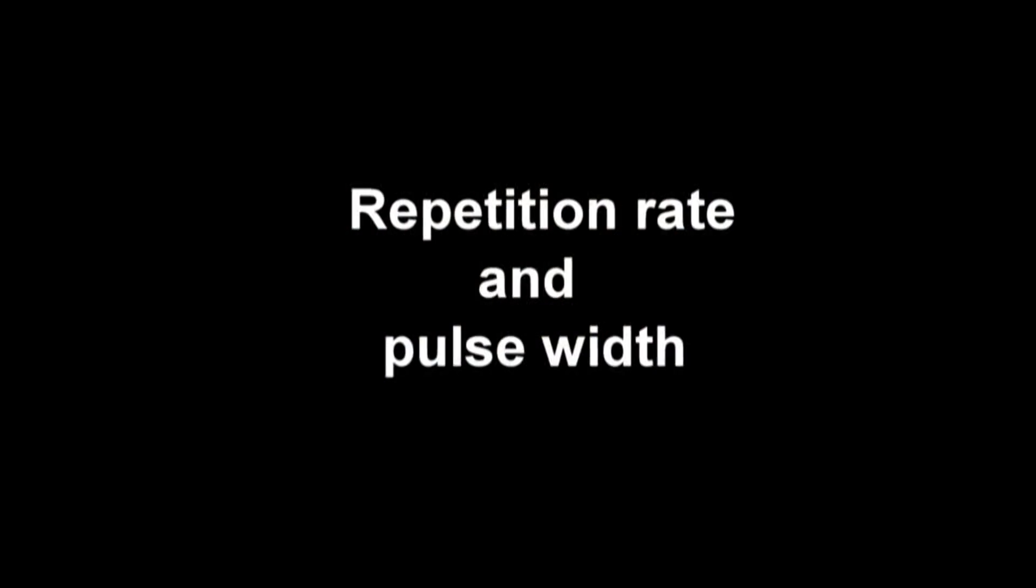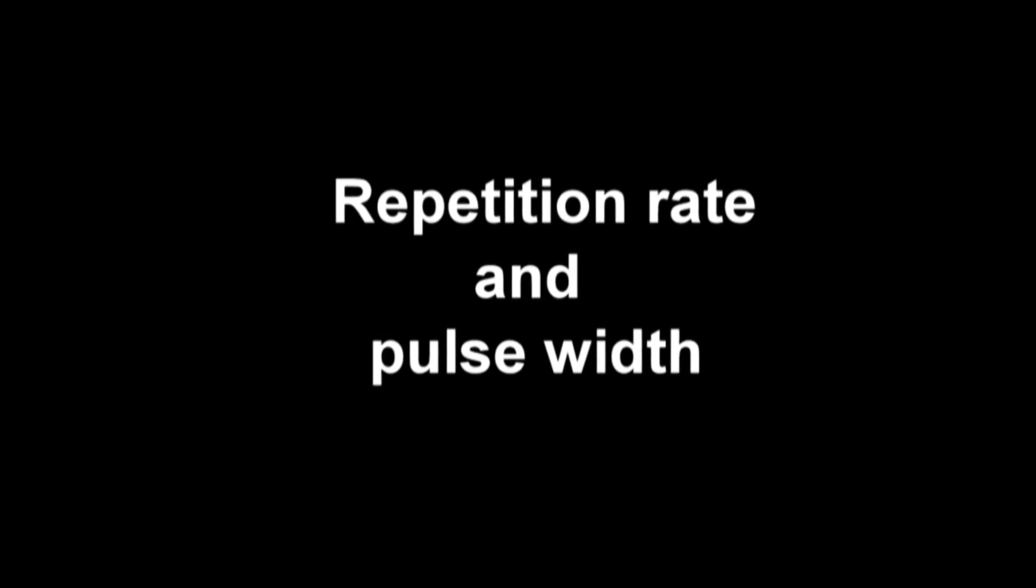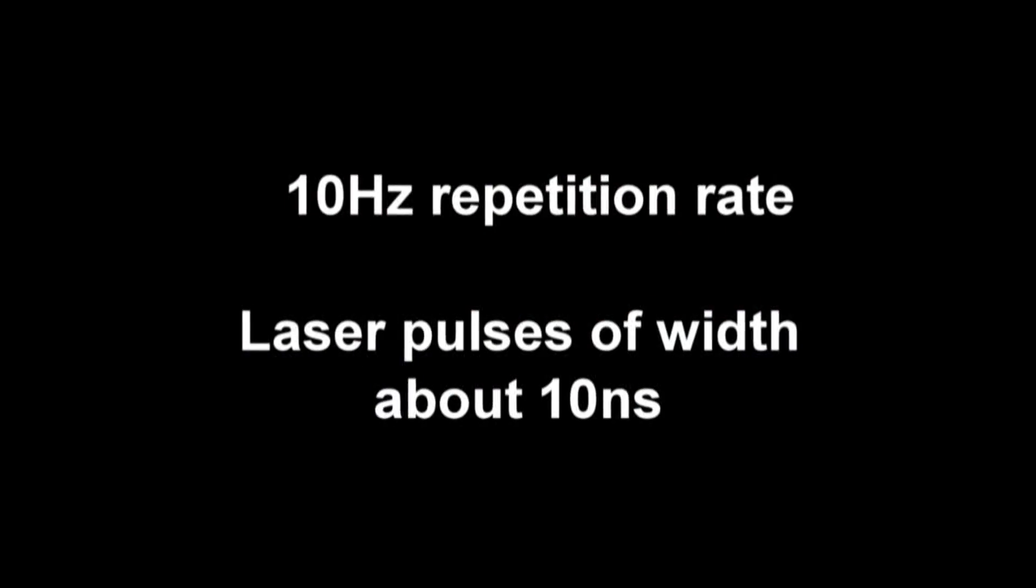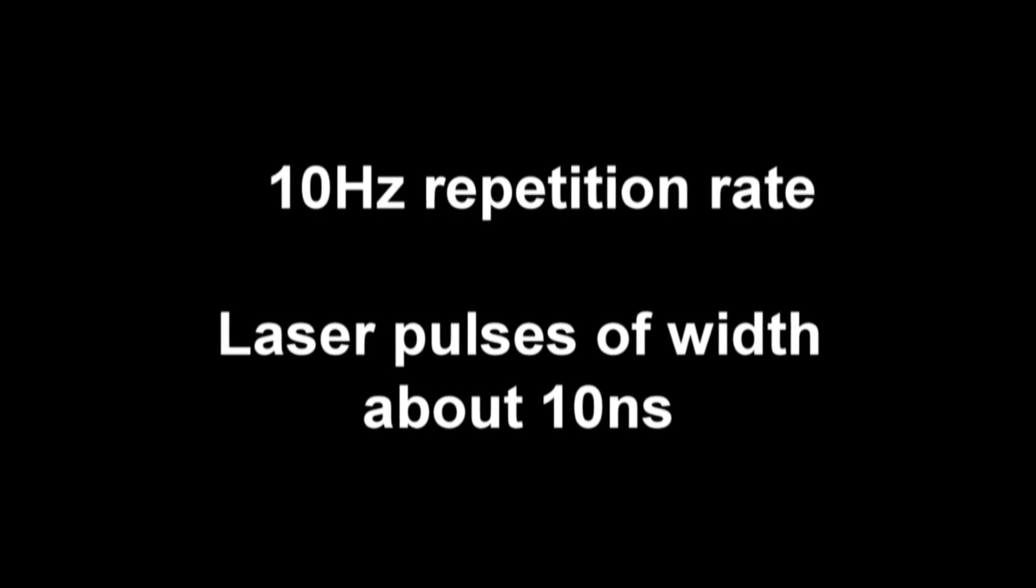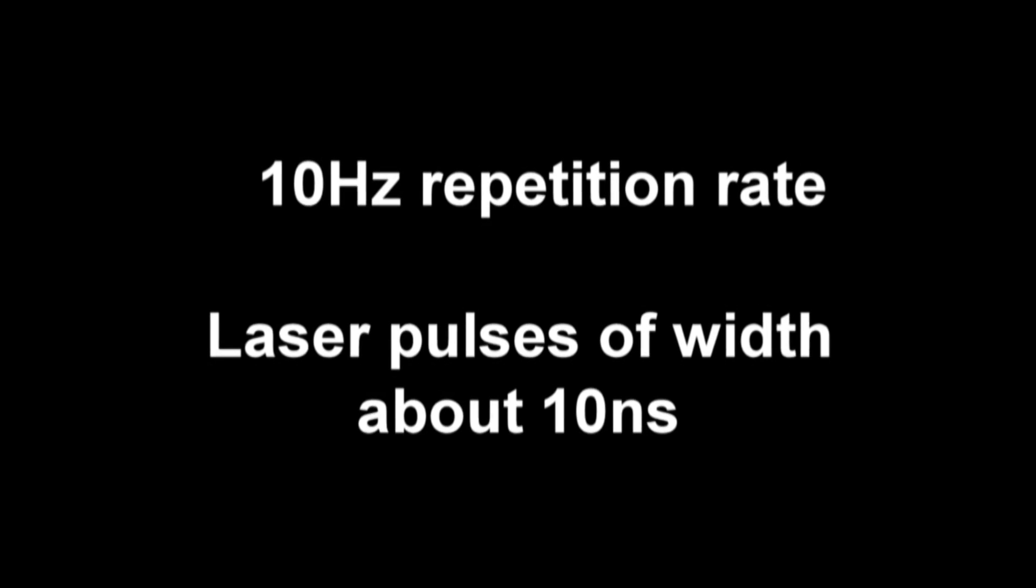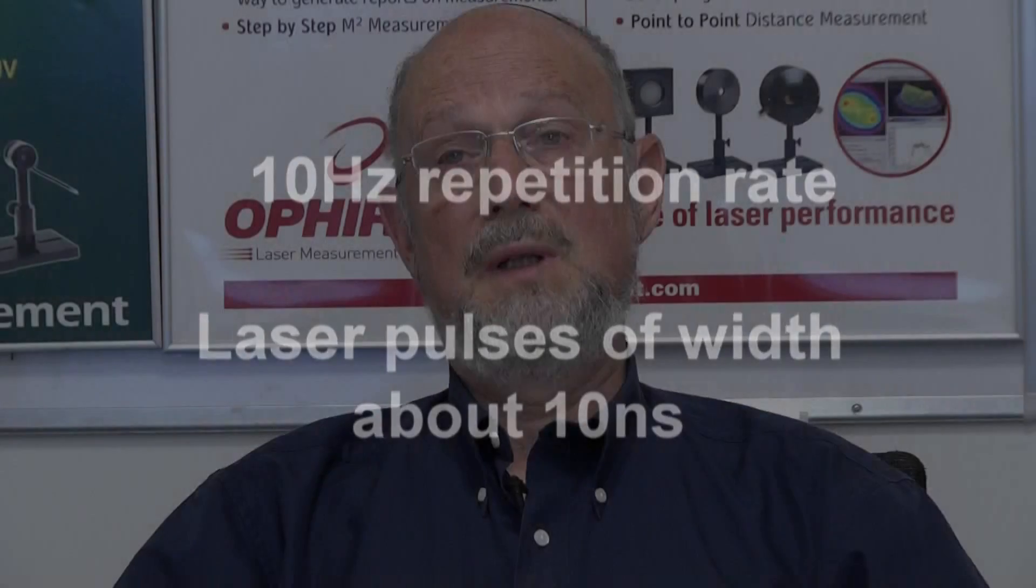Now there are other sources of error that are possible for pulsed lasers. When we want to measure the energy of a pulsed laser, there are two more things that have to be taken into account: the repetition rate and the pulse width. Now we usually calibrate our meters at 10 Hertz repetition rate and laser pulse widths that are rather small, about 10 nanoseconds. This is typical for commonly used YAG and harmonic lasers.